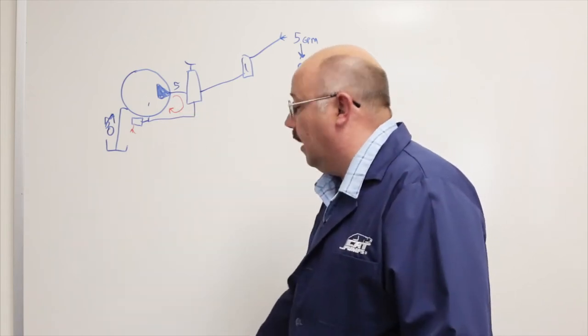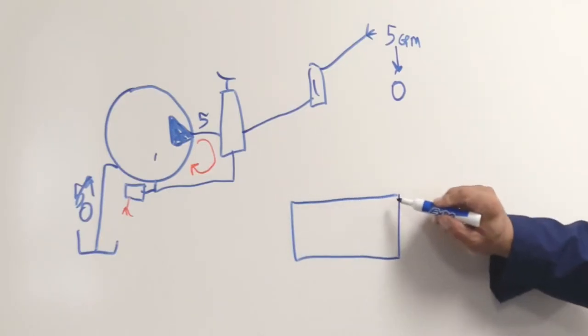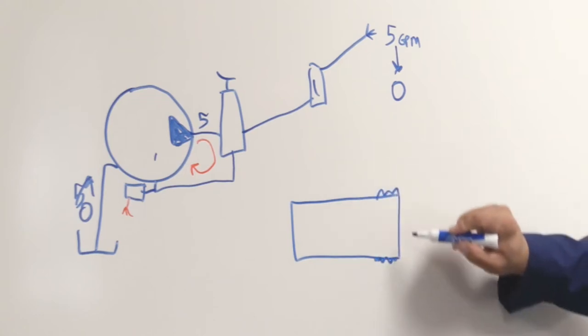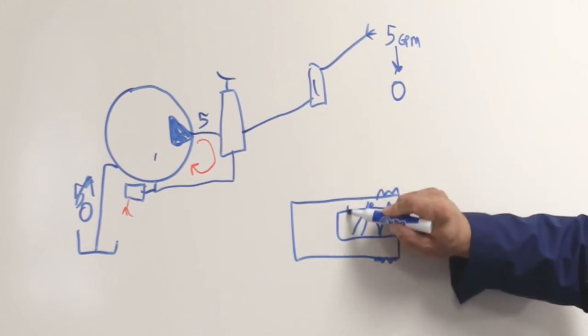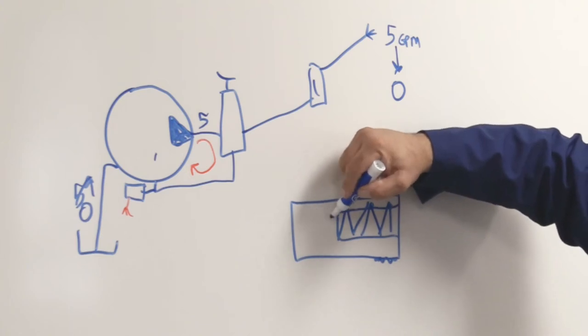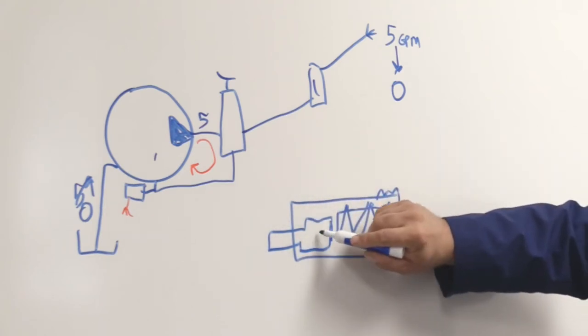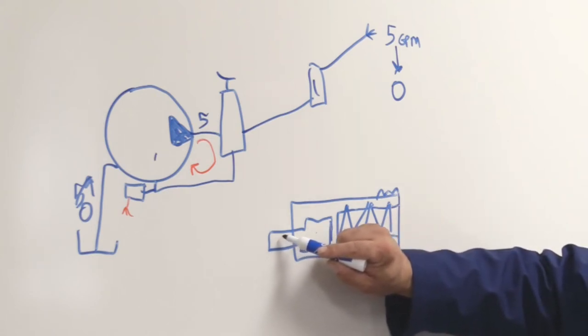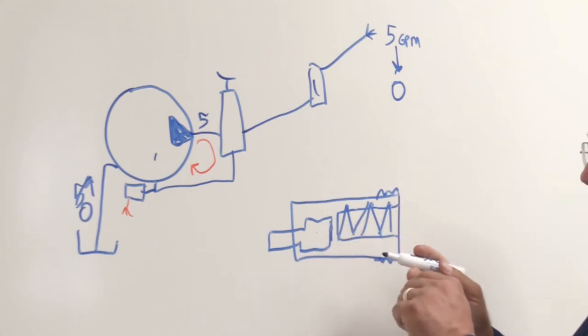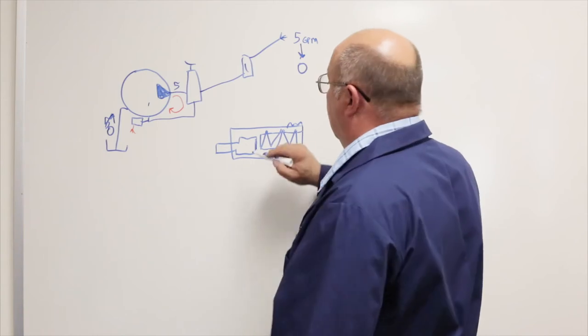Now, what's really happening inside that thermal valve is what we're going to cover next. So I'm going to draw it in a much larger scale. Here we have the inlet body. And of course, there's threads here so we can thread it in. Then there's a large spring in here, a cavity for the spring. And then there's what we call a pill. It's shaped like this. And it has a copper head for good heat transfer. And then this pill is filled with wax and there's a plunger on it that as that pill heats up, that plunger goes forward and it will open up. Now, that's the same type of pill that you'll see in an automobile thermostat. So it's a very reliable piece of equipment.